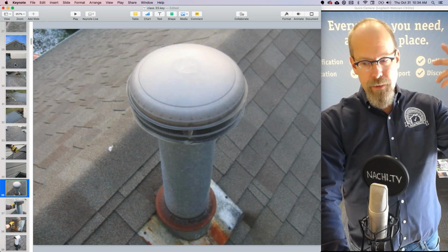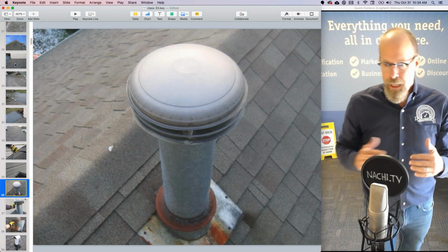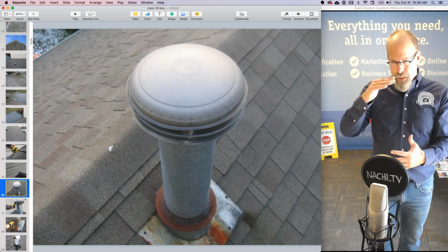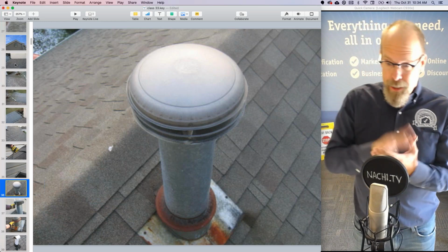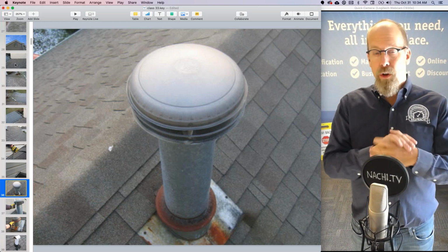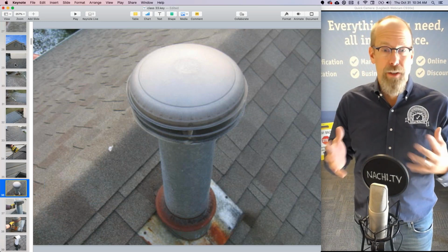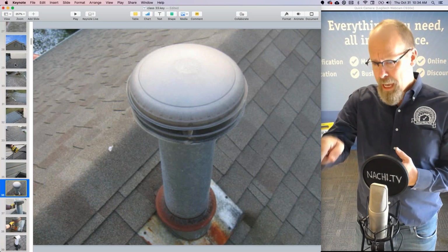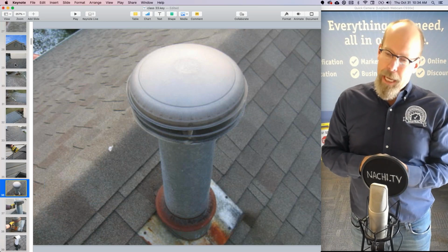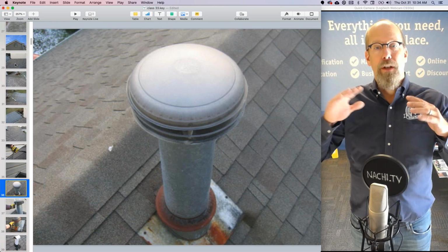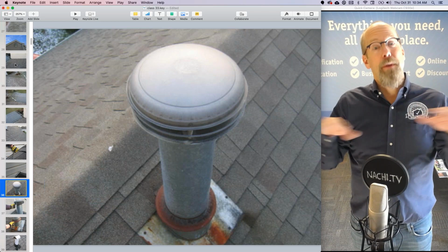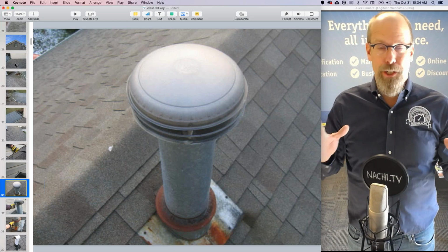There's a gas furnace. There are some stack minimums. That's in the code as well. And it's in the InterNACHI online courses about how to inspect furnaces and chimneys. That's a gas vent pipe. And what I want it to be is at least 2 feet off the surface of the roof. And if there's anything within 10 feet, it's kind of like a masonry chimney.